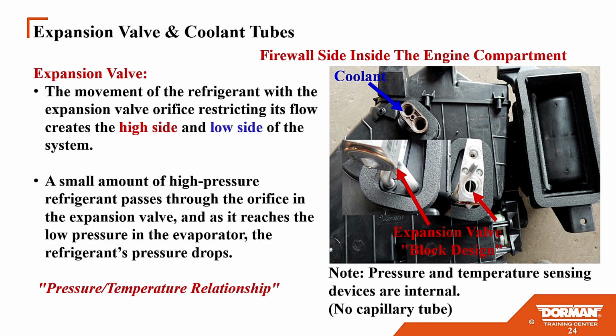The expansion valve, a little better explanation: movement of refrigerant with the expansion valve orifice restricting its flow creates the high side and low side. Basically, a small amount of high pressure refrigerant passes through the orifice in the expansion valve, and as it reaches the low pressure in the evaporator, refrigerant pressure drops. So again, we have the pressure-temperature relationship, okay.